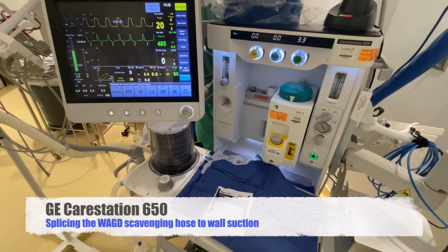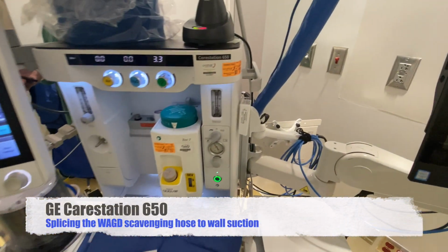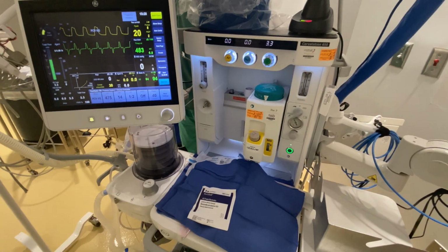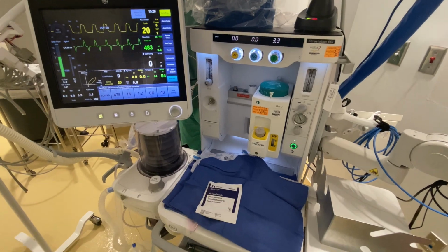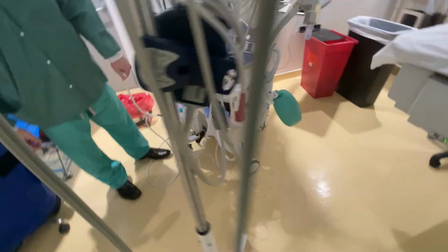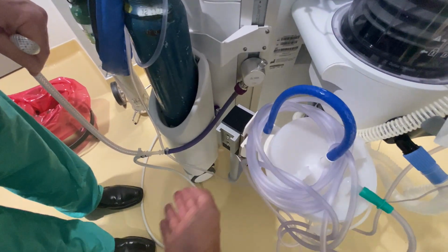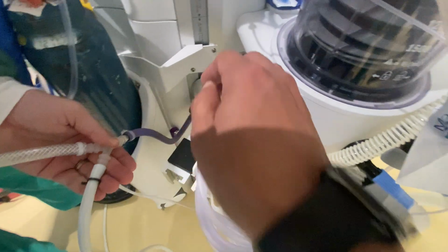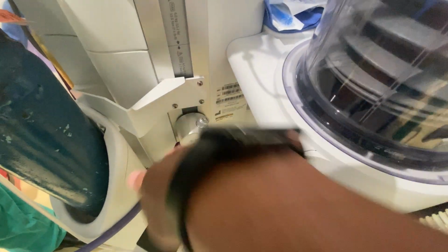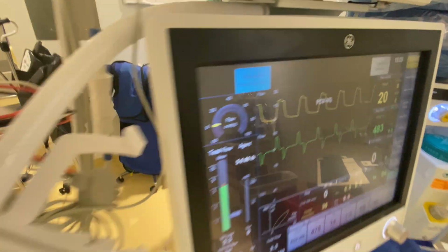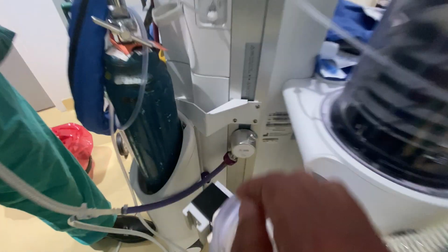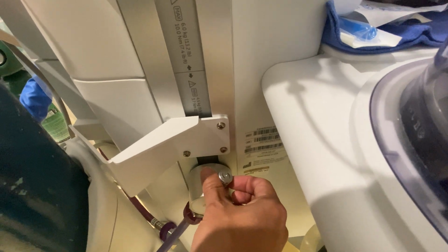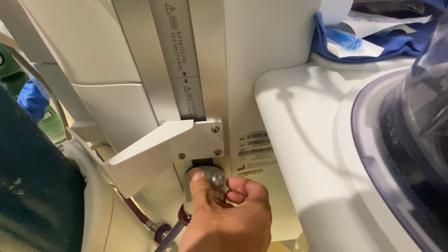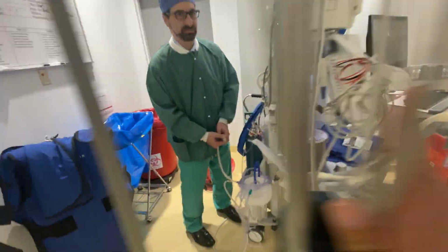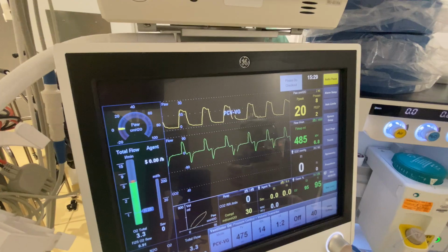As part of the review of other types of equipment, just a quick little note and variation. If you happen to be using a CareStation 650 that does not have a balloon-based scavenging system, walk along with me over here. To this side you'll notice that we've got our Y set up to the medical grade vacuum, and if you were to twist the valve on the scavenger all the way closed, you get a notice that the scavenging flow is too low. So given that you have normal high suction on that, we figured out that it's about 2.5 rotations. So here we go, 1/2, 2/2, and then right there, it should go away. That's the sweet spot. See? Too much, too little, just right.